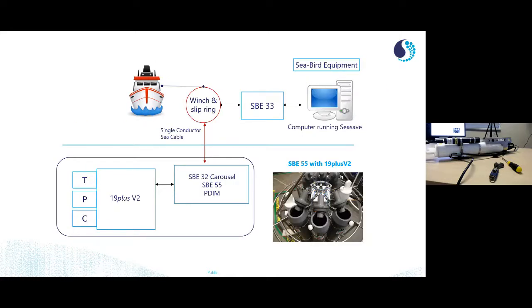Alternatively, if you have more equipment on your research vessel, such as a winch and slip ring with a conducting sea cable, the 19 plus V2 can be integrated with a water sampler or the PDIM, Power Data Interface Module, to communicate in real time. This requires more equipment. On the bottom left, we have our 19 plus V2 measuring temperature, pressure, and conductivity, connected to an SBE 32 water sampler, SBE 55 water sampler, or the PDIM. That handles the voltage and converts the RS-232 communication from your CTD to DPSK, sending it up the winch and slip ring to your SBE 33 deck unit, which handles the power, reconverts the signal from DPSK to RS-232, and sends that data to your computer, running Seasave or similar software that collects the data.